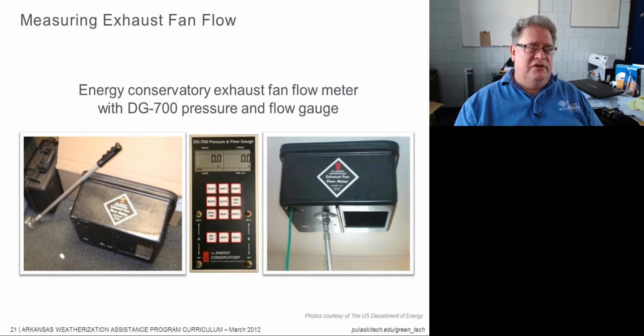I'm going to caution you against using it that way, because hooking it up incorrectly is very easy to do. If you do it, make yourself a sticker or something. Tape something on the side of this exhaust flow meter, so that you know how to hook that manometer up each and every time, or carry the instructions. Otherwise, it's a little easier to ignore the fact that we have a device on there and get a reading directly off this machine and just look it up on the table. Sounds like there would be more room for error, but in my experience, no, there's less room for error. I'll show you in a video some of the hazards of it. It's a good device. You just need to be careful with it.